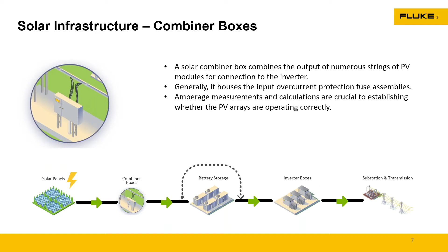This definitely houses your overcurrent protection, like your fuses. But this is a great place for a technician to go out and start troubleshooting as well. They can open up the combiner box and make sure that the amperage is equal on all of the different strings, maybe the voltage. It's a good way to go in and check if you have any ground faults happening. You can go here first to identify that and then move out into the system and determine where that's happening.